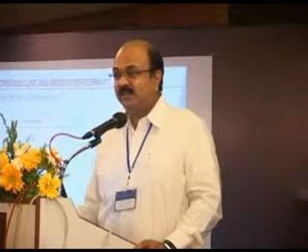So what we want to summarize here is that you are not looking at an improvement from where the boiler was originally operating. It was designed for 85%, now we are giving 86. That's not what it is. In most R&Ms, you will see that the efficiency has already gone down by 5%. 5% out of 80 is more than 5%. Like that, you have something for the turbine. So in net effect, you can reduce your coal consumption for the same megawatt you produce by at least 10 to 15%. That scope will always exist in most R&M cases. And you are also reducing the power consumption itself, so that's also going to add to the cycle.